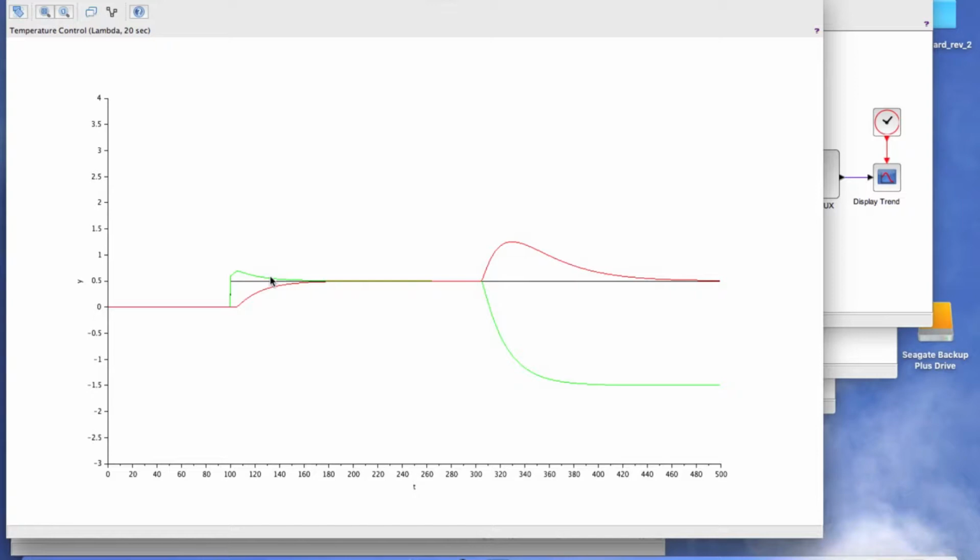The valve position does not change nearly as much compared to Ziegler-Nichols, and there are no oscillations in the valve position. For lambda methods, the objective is to manage a set point change within the specified response time with no overshoot on the process variable. This also avoids oscillation in the valve position.